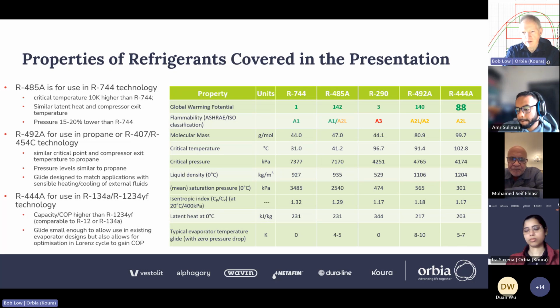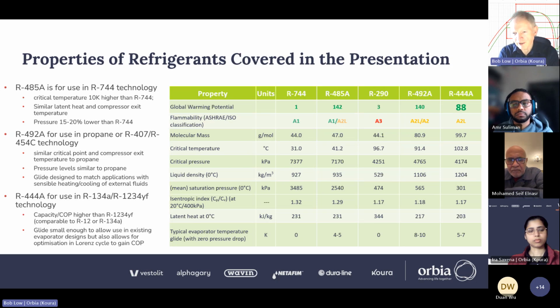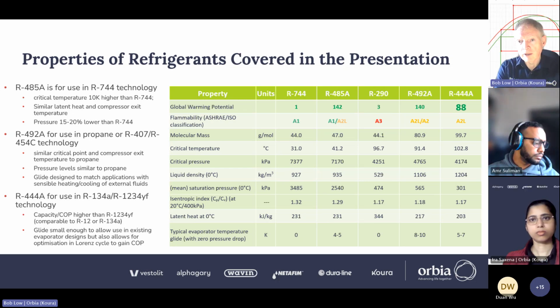And finally, 444A, which is really a medium pressure refrigerant. It's the same sort of pressure level as 134A or 1234YF. However, unlike those fluids, it's actually a higher efficiency than 1234YF. It's closer to R12, in fact, than to 134A in performance. Very few people will have seen an R12 system these days, but it was more efficient than 134A in its own right. It was just pretty bad for the ozone layer. So the reason for including 444A is that it also has temperature glide. It's smaller, about 5 to 7 degrees, depending on the cycle conditions. But it can be used also in a Lorenz cycle configuration to give itself another 5 or 6% COP over what would otherwise be achievable.